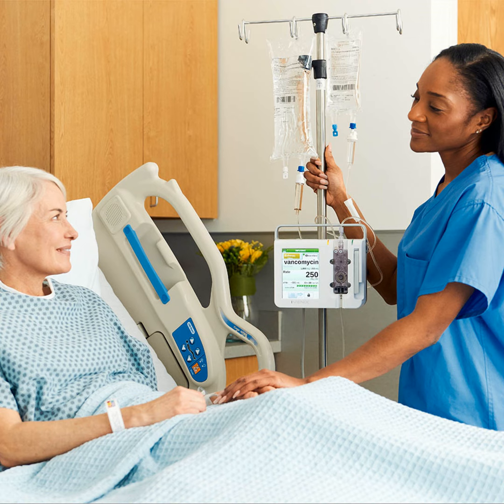Also, the drug library should always be updated on those pumps. And when I say update it, you shouldn't have multiple drug libraries in place at the hospital that could cause errors. And second, you want to make sure that updates to the drug library are completely invisible to the nurse. So you don't want them accepting it and then rebooting the pump. That's unacceptable. You want it to happen naturally, and you're operating the pump and bloop, the drug library is updated. Now, if you go down the stream of automation, the advanced pump should also sense when the downstream tubing is occluded. So it should recover when the obstruction is resolved.